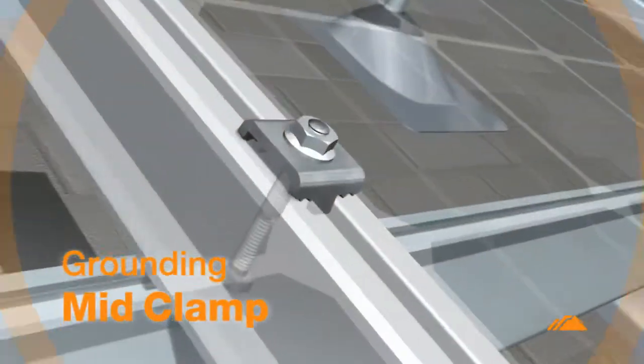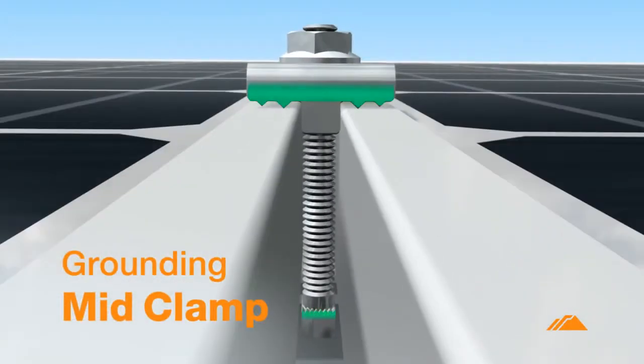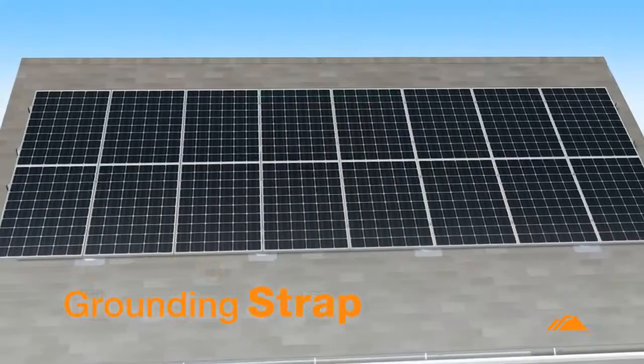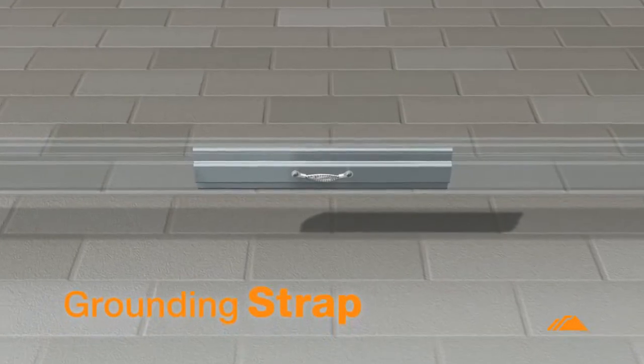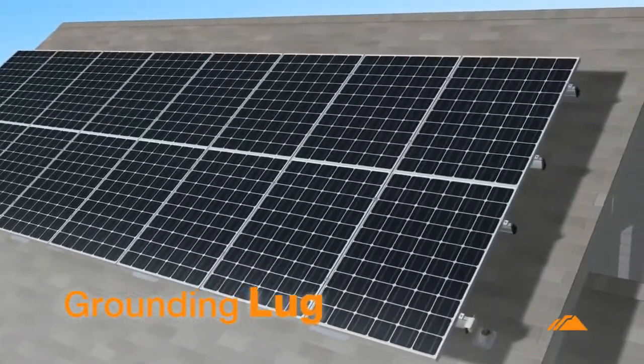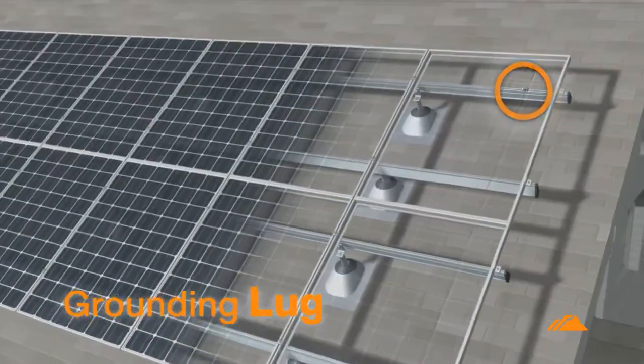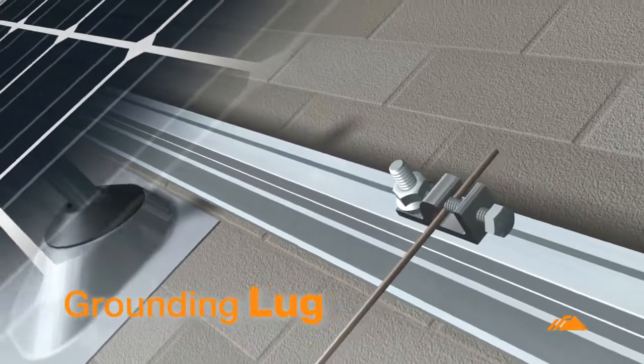The grounding mid-clamp uses teeth on both top and bottom to bond solar modules and rails into one continuous system. The grounding strap combines with a rail splice to structurally and electrically bond two segments of rail. And the grounding lug connects the entire row of modules to a grounding conductor.